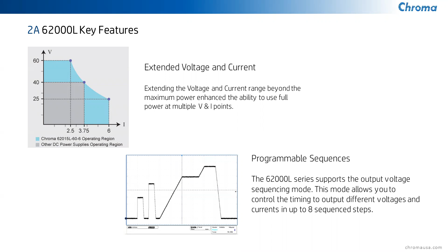Programmability for this unit is great. It gives you up to 8 sequences. Each one can be programmed in 500 millisecond steps. You can set these units at different ramp rates, and you can also do it over different periods of time. We already talked about these units can be paralleled, so you can parallel up to 7 units. With 7 units, you can get up to 49 amps of maximum current, and with 4 units in series, you can get up to 240 volts DC max.